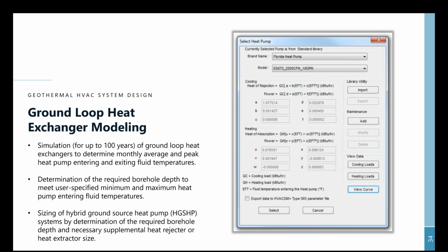It will determine the number of required boreholes and what depths those boreholes need to be in order to meet your specified criteria. And that criteria specifically is your minimum and maximum heat pump entering fluid temperature. Various pieces of equipment can operate at different temperatures, so it's very important to establish those parameters early on to get accurate modeling information.